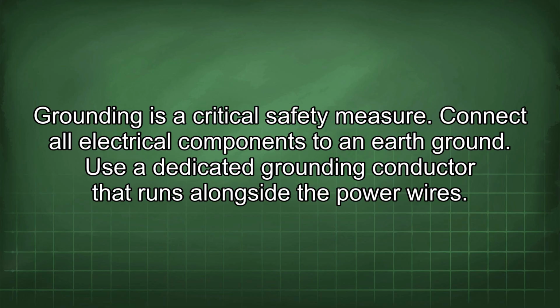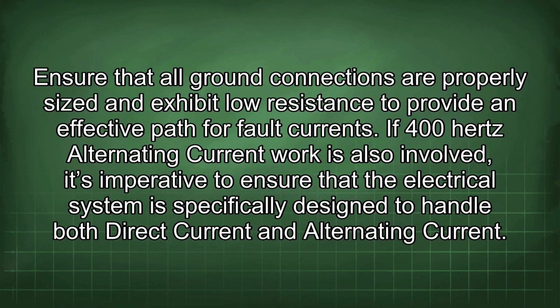Grounding is a critical safety measure. Connect all electrical components to an earth ground. Use a dedicated grounding conductor that runs alongside the power wires. Ensure that all ground connections are properly sized and exhibit low resistance to provide an effective path for fault currents.